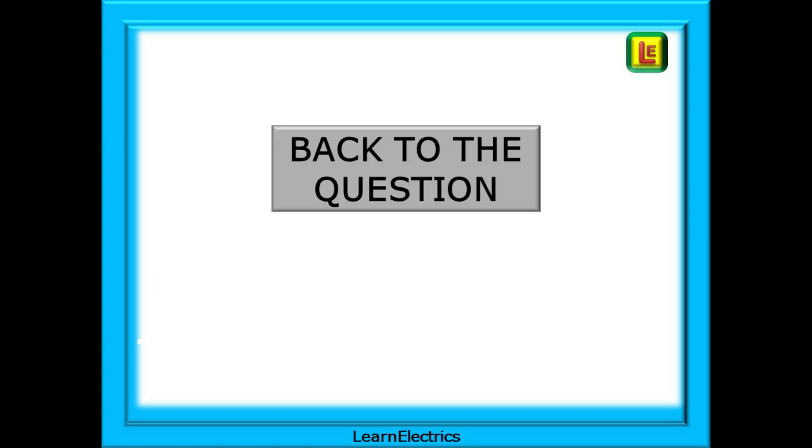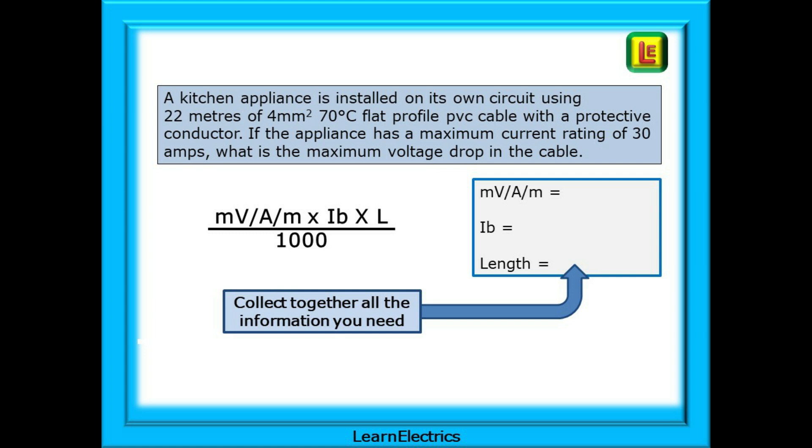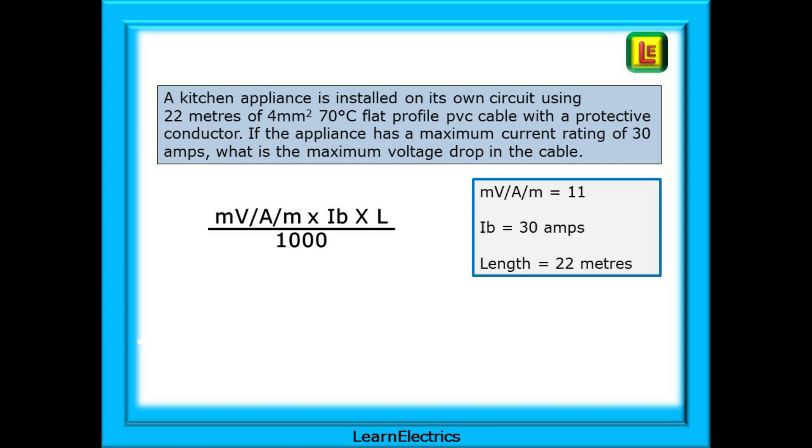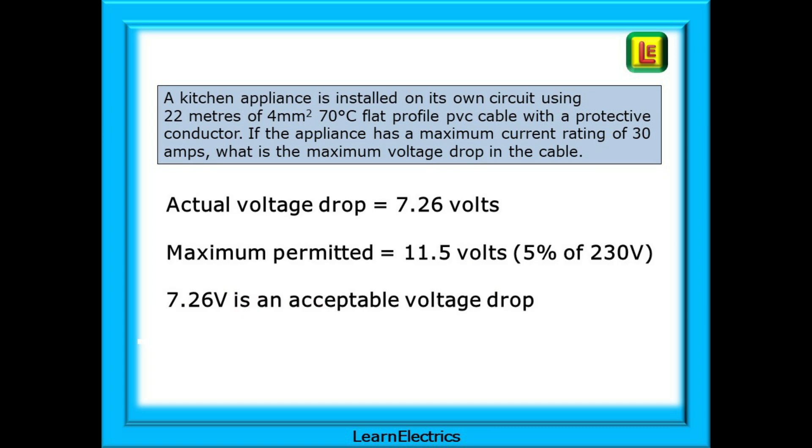Back to the question now. Here's the question and the formula. To help us to put the numbers into the formula I always write down on the right hand side of the page all the numbers that I need to know. And now I can extract each of these numbers from the question or from the tables. I've done it this way for 40 years, it's an organised way of doing things and it works. It keeps you in control of the question and you can easily trace where you went wrong if you have a problem. Put the numbers into the equation and out comes your answer. Our actual volts drop is 7.26 volts. This is well below the maximum permitted value of 11.5 volts, the 5% figure for non-lighting circuits.